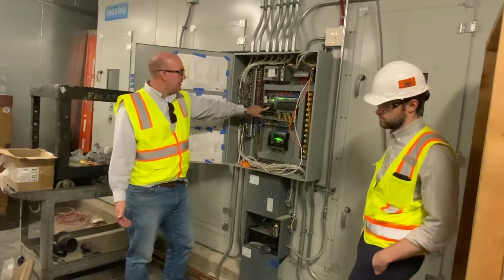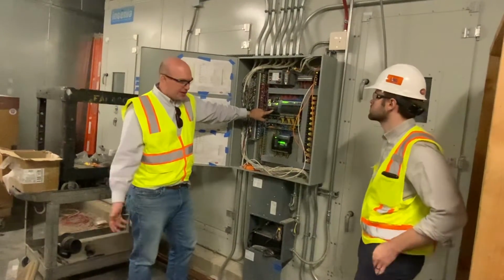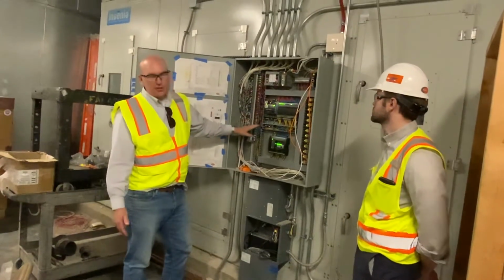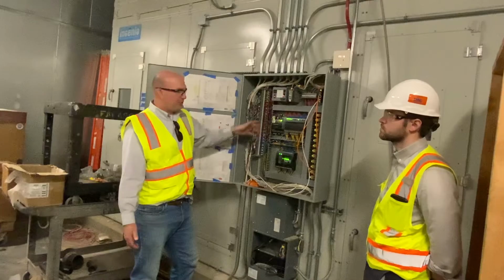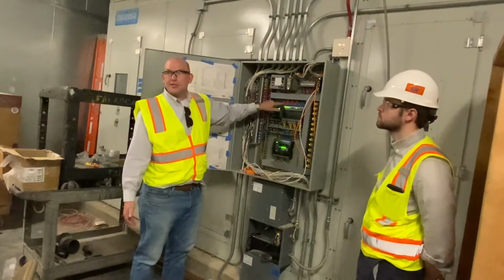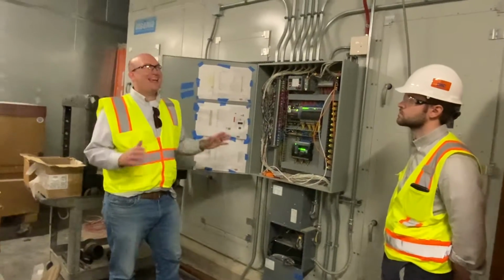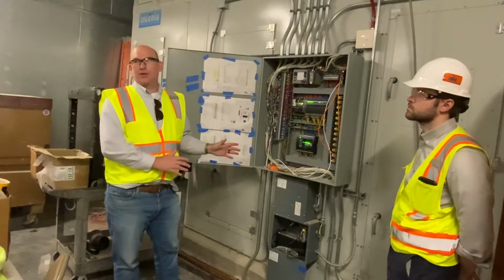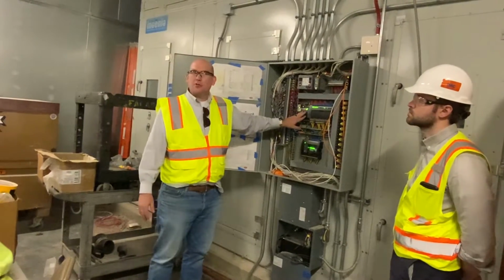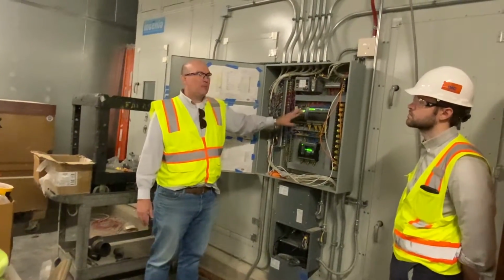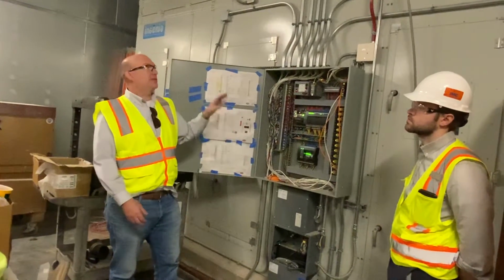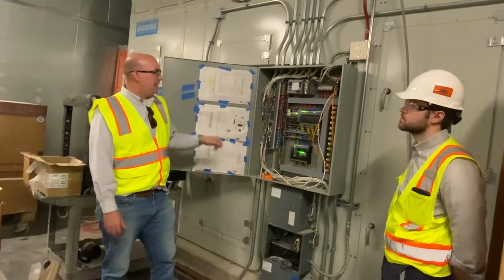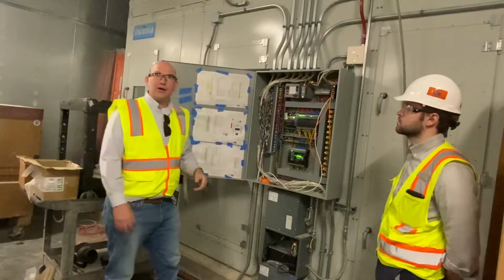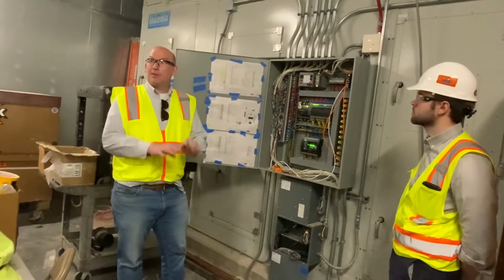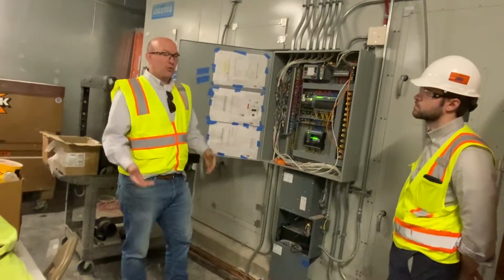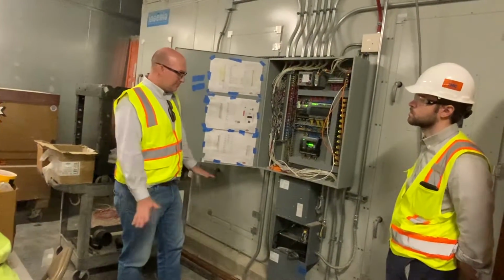If you did need to get into the controller and make a change to, say, its IP address, anything like that. That gets me to another major shift in how things are handled for Automated Logic. These are all network devices. They have an IP address. There is a dedicated BAS network that is separate from the building's network, so you don't have to talk to an IT department to IP address this. You don't have to go through a firewall. These are all on a dedicated IP network that is just for building automation equipment. And you can plug into this, and we have a DHCP server. So you basically plug your laptop in and get right in, just like when you sit at your desk. Don't have to worry about anything in that regard.